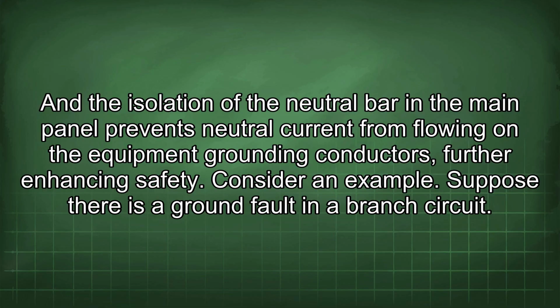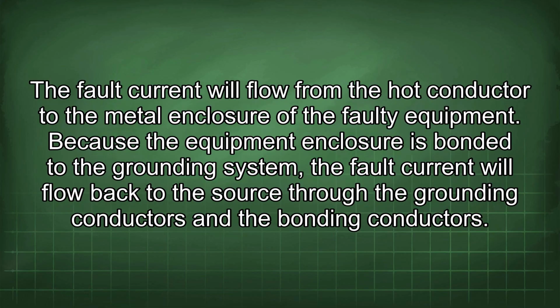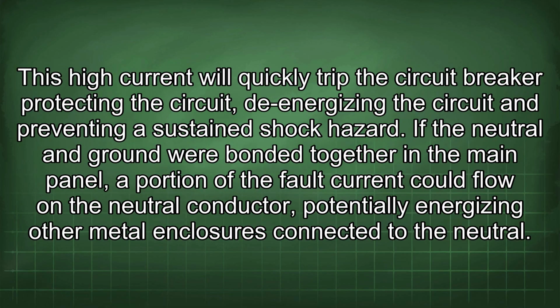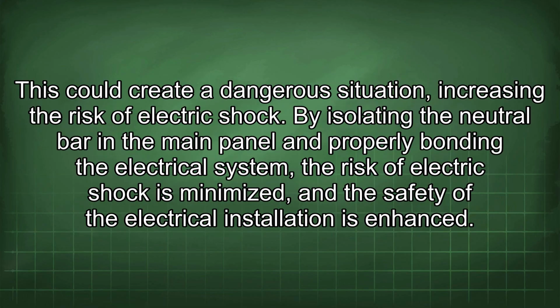Suppose there is a ground fault in a branch circuit. The fault current will flow from the hot conductor to the metal enclosure of the faulty equipment. Because the equipment enclosure is bonded to the grounding system, the fault current will flow back to the source through the grounding conductors and the bonding conductors. This high current will quickly trip the circuit breaker, protecting the circuit, de-energizing the circuit, and preventing a sustained shock hazard. If the neutral and ground were bonded together in the main panel, a portion of the fault current could flow on the neutral conductor, potentially energizing other metal enclosures connected to the neutral. This could create a dangerous situation, increasing the risk of electric shock.